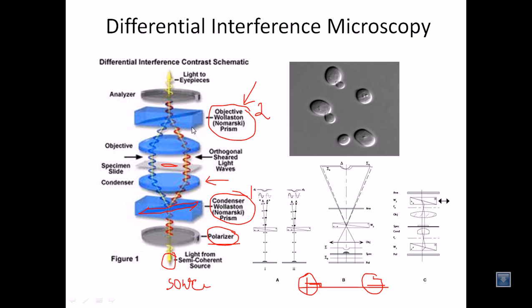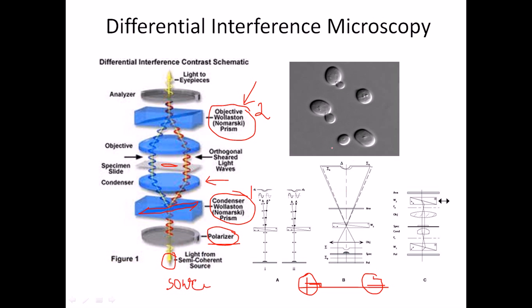After passing through the analyzer, when there is no specimen, all the light beams that passed through the blank slide — traveling via the objective and second Wollaston prism — are excluded by the analyzer. No light, or a very fine amount of light, passes through, which cannot create any image. Therefore we see a dark background without any specimen.